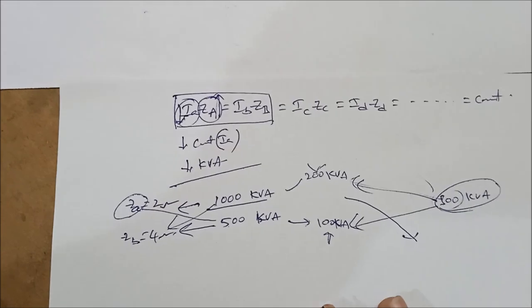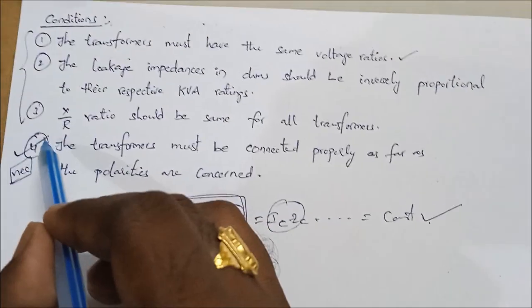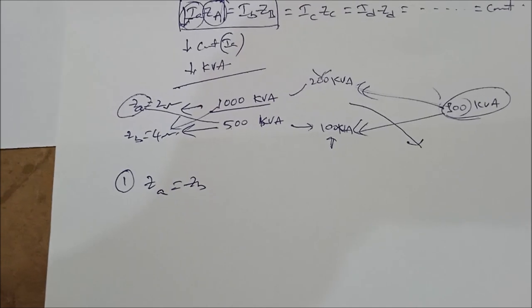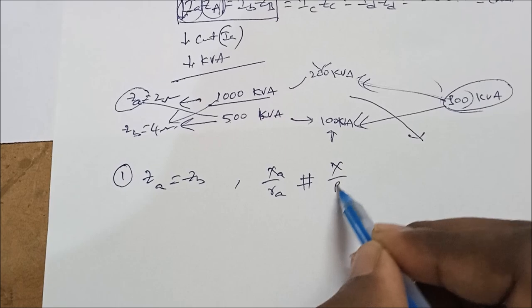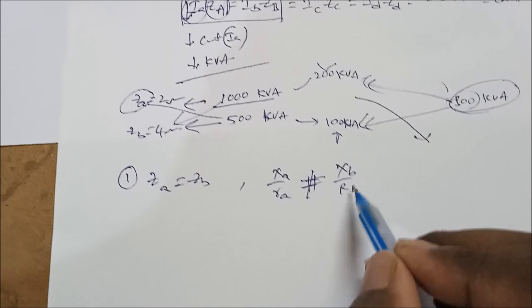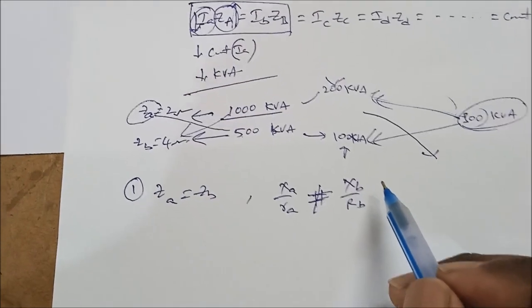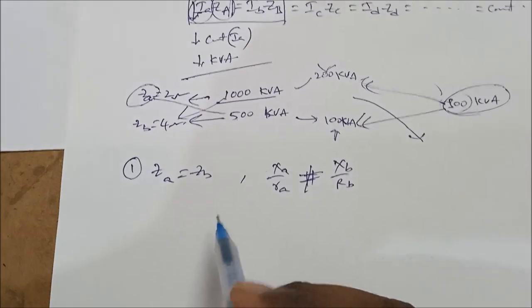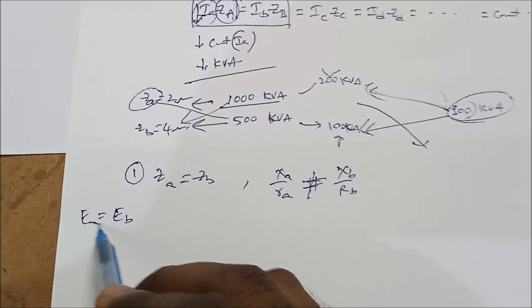Now let us go to the third point: the X/R ratio. Consider Case 1: Za = Zb, but the X/R ratio of the first transformer is not equal to that of the second — Xa/Ra ≠ Xb/Rb. This is a desirable condition but not a necessary one; even if X/R ratios are not equal, transformers can still be connected in parallel. We continue assuming equal voltage ratios, i.e., Ea = Eb.